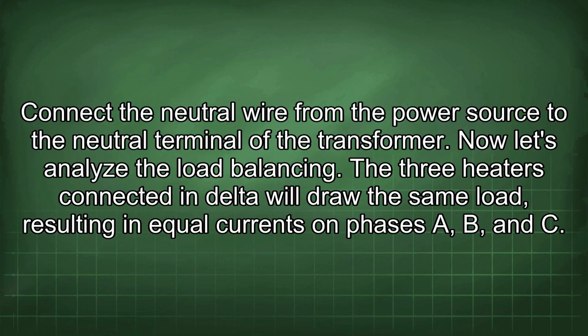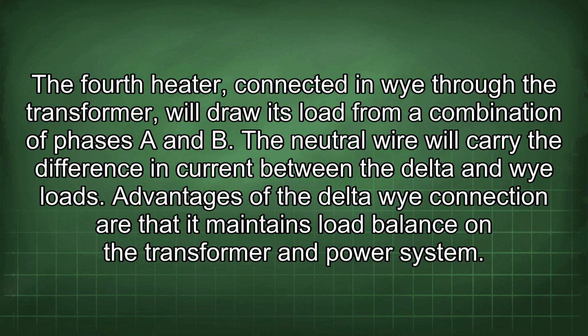Now let's analyze the load balancing. The 3 heaters connected in Delta will draw the same load, resulting in equal currents on phases A, B, and C. The 4th heater connected in Y through the transformer will draw its load from a combination of phases A and B. The neutral wire will carry the difference in current between the Delta and Y loads.